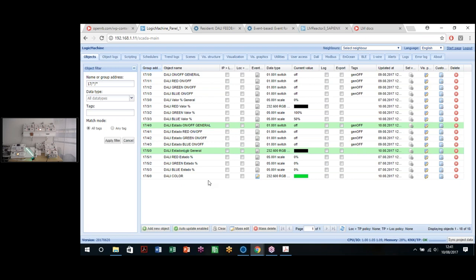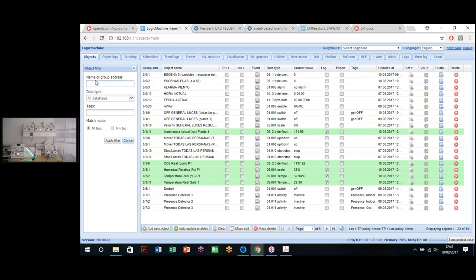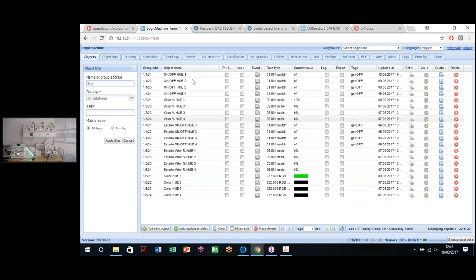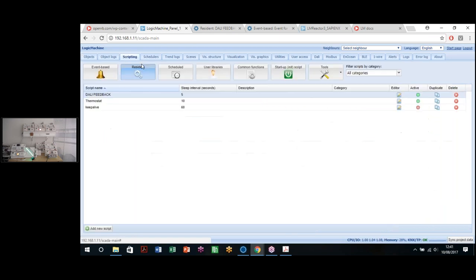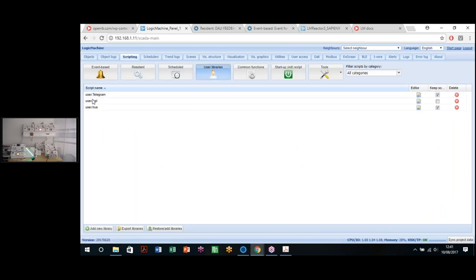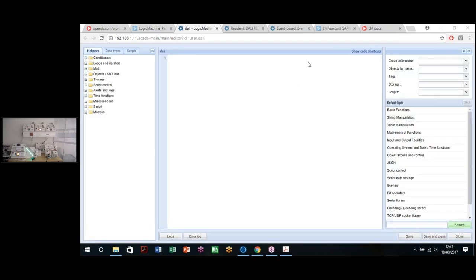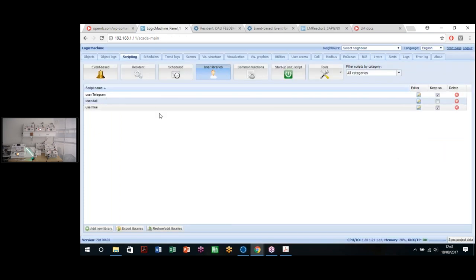Now let's configure some Philips Hue lighting. For that, I have created a certain number of objects that I've called Hue. In this case, we can see that we have a lot of Hue objects. For configuration of these Hue objects, we need to use a user library in the scripting tab. The user library, as with the DALI configuration, we can find in the examples tab of the LogicMachine OpenRB webpage. We have all the information there to create this integration. I clicked the wrong one. I clicked DALI. Let's go to Hue.